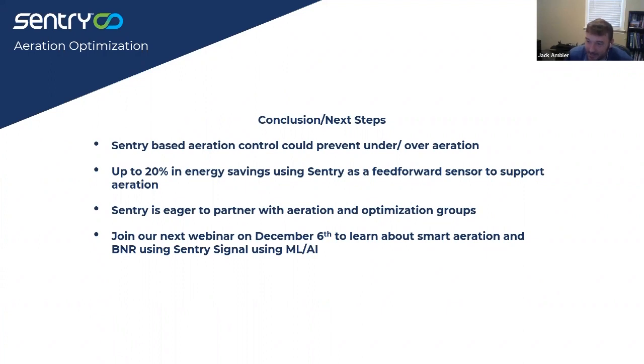He just said, looks like they have pretty bad DO control in the first place. They need to fix that to understand the benefits that SENTRY can give. And I'll start on that, and I can maybe throw it over to you as well, Manaz. But yeah, I definitely think it's a great point. I think it's actually a helpful case for us because we can really see the results of the poor aeration, or the way that they don't handle the load well. So it does give us a nice positive reaffirmation, without enough intervention from their aeration system.